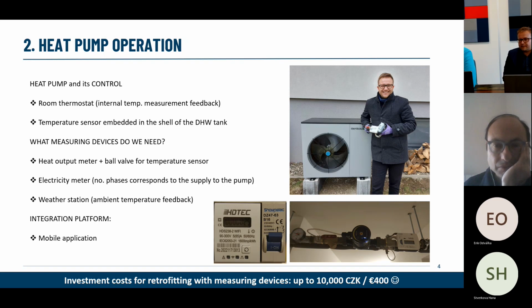There are multiple ways to address this, but a very straightforward approach is to ask the heat pump installation company to also install a calorimeter, or power flow meter, if you like. That's the white box in the bottom right picture on the right-hand side, and it measures the temperature difference between the inflow and outflow pipes of your heating system.